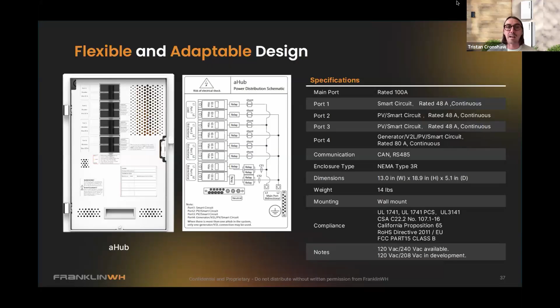To give you an idea of the versatility here, any of these breaker spaces can be used for smart circuit or load management. Now, why would you use load management? Maybe it's a single battery installation, you're using a meter collar, and it's now automatically a whole home backup. That single battery could drain very quickly if there were, say, multiple AC units. With that being said, you can connect those AC units to the A-Hub.